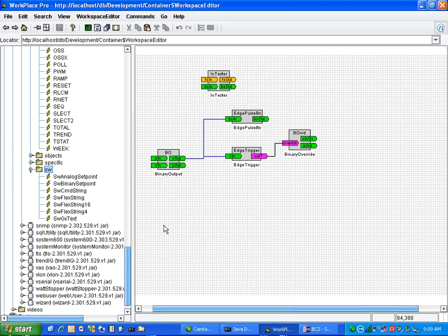In today's world, we find out that I don't want 2 decimal places. That's silly. But when we do external links, we lose the ability to control the number of decimal places, because external links will always resort back to 2 decimal places. And if we're linking externally right to a graphic screen, we're kind of hosed in a way.